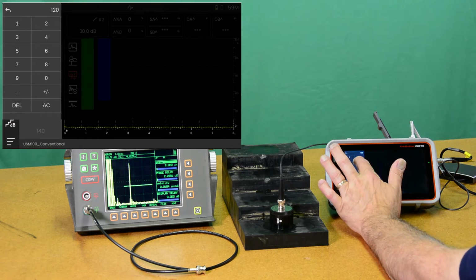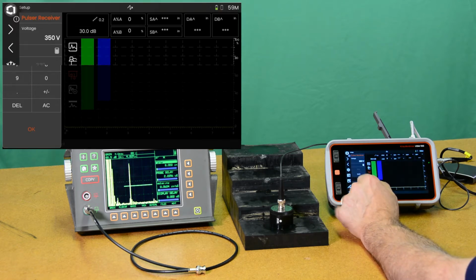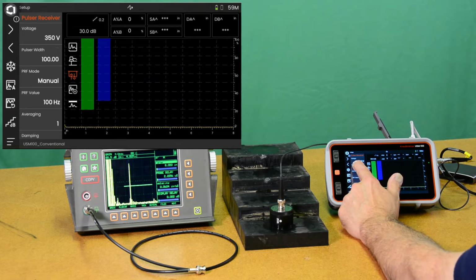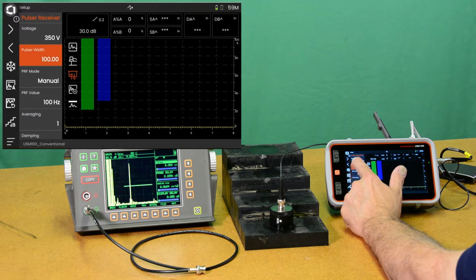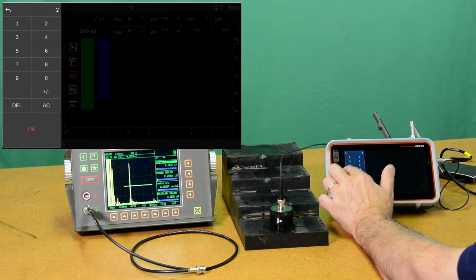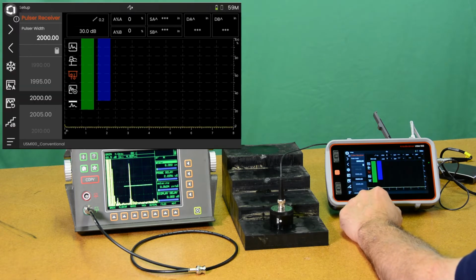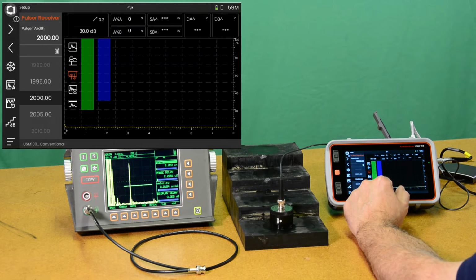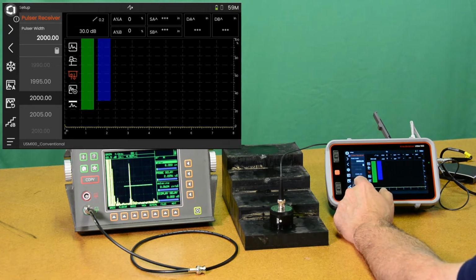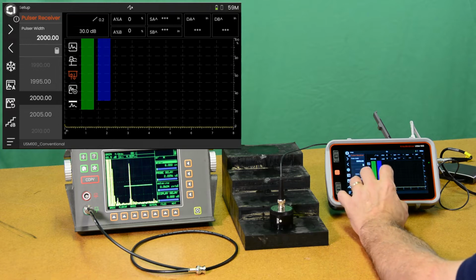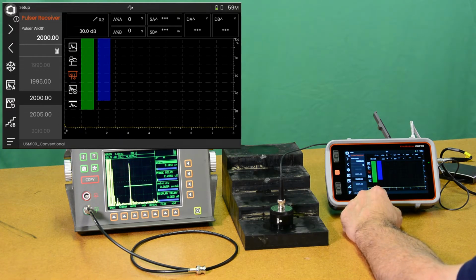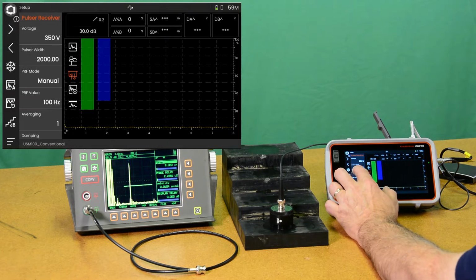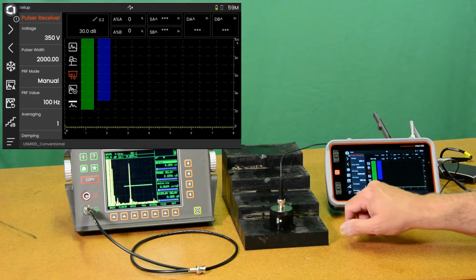Okay, we're going to max out our pulser at 350 volts. And we're going to take our pulse width to, let's set that to 2000 nanoseconds. So for the 500 kilohertz probe, one complete cycle of the ceramic is going to be 2000 nanoseconds, 1 over 500 kilohertz, 2000 nanoseconds. Ordinarily half wave, so about half of that would do well. But I found with this pulser, all the energy we can give this probe is the best performance that we get out of it. So we're going to call that 2000. And then we're going to close that menu.